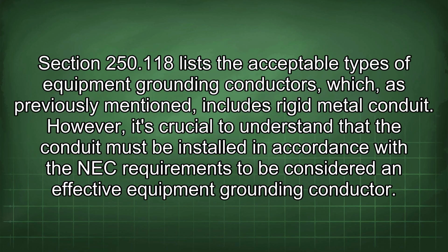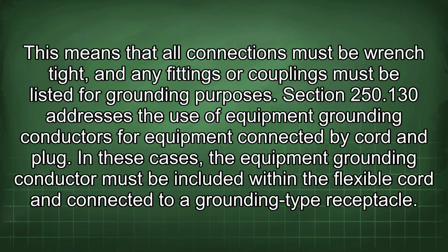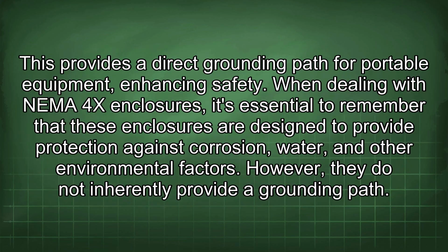Section 250.118 lists the acceptable types of equipment grounding conductors, which, as previously mentioned, includes rigid metal conduit. However, it's crucial to understand that the conduit must be installed in accordance with the NEC requirements to be considered an effective equipment grounding conductor. This means that all connections must be wrench tight, and any fittings or couplings must be listed for grounding purposes. Section 250.130 addresses the use of equipment grounding conductors for equipment connected by cord and plug. In these cases, the equipment grounding conductor must be included within the flexible cord and connected to a grounding type receptacle. This provides a direct grounding path for portable equipment, enhancing safety.